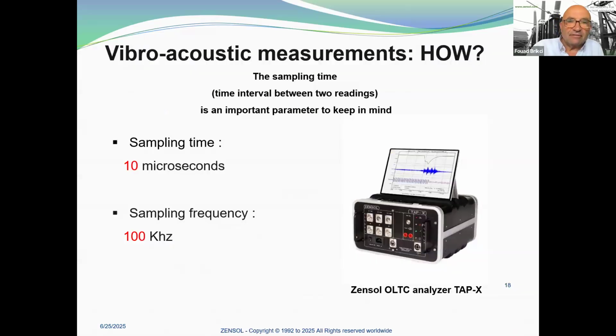Okay, so vibroacoustic. The sampling time, the time interval between two readings, is an important parameter to keep in mind. Usually, for all our vibroacoustic measurements, we use 10 microseconds, which is a sampling frequency of 100 kilohertz.